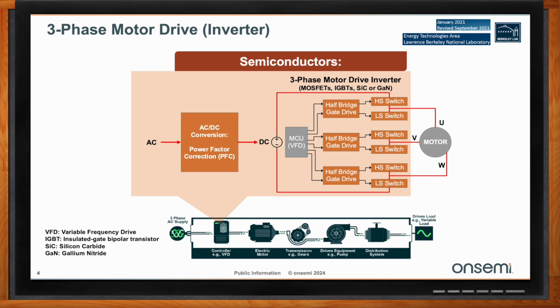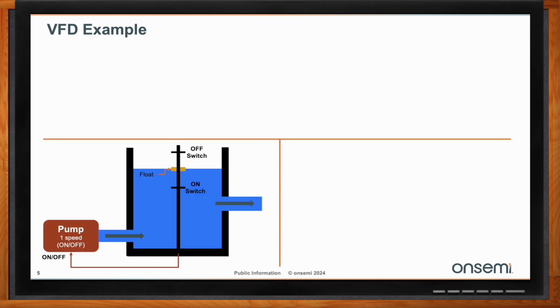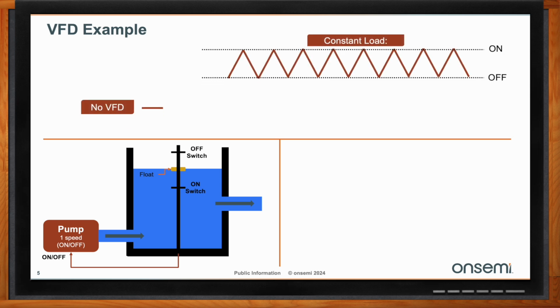Okay Bob, can you explain the variable frequency drive a bit more? I sure can. On the bottom left of the screen, you can see I've got this reservoir of blue liquid and a 1-speed pump that's pumping that liquid into the reservoir, and on the right there's some sort of output. In the middle there's a float, your classic float, connected to a switch that's fed back to the pump. If the reservoir gets too low, the pump turns on. If it gets too high, the pump turns off. It works great for many, many years.